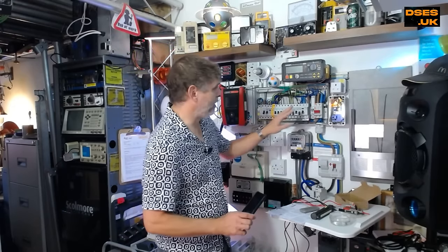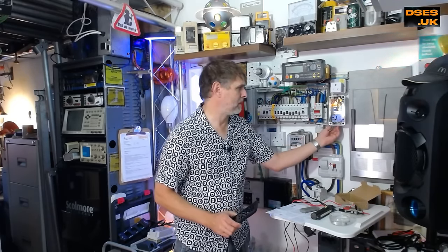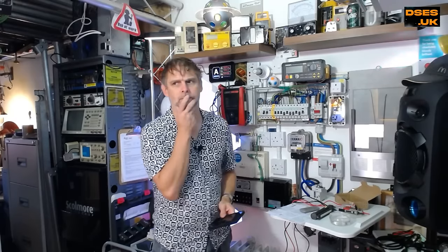The Hager unit is now installed and I've removed the front cover from my arc chamber so we can all better see what happens as it happens. It's not ideal to have covers removed and live parts exposed, but I'm trying to show things in action here and my hangover has just about cleared enough for me to be considered a skilled person. Perhaps.